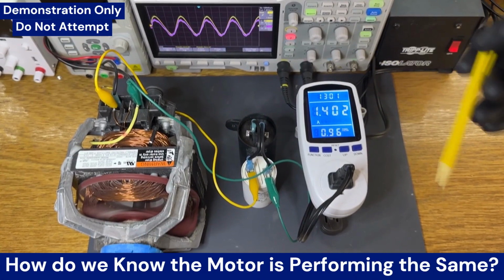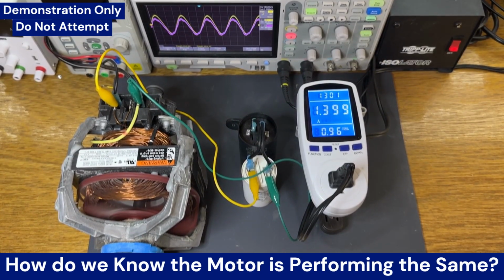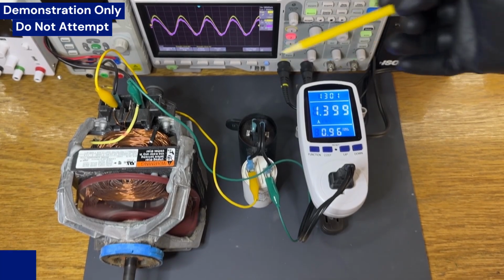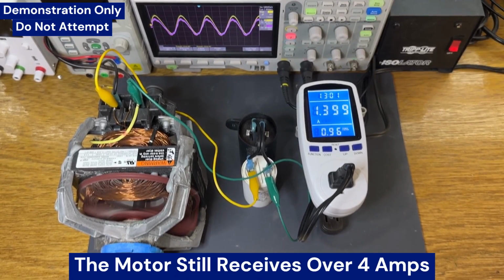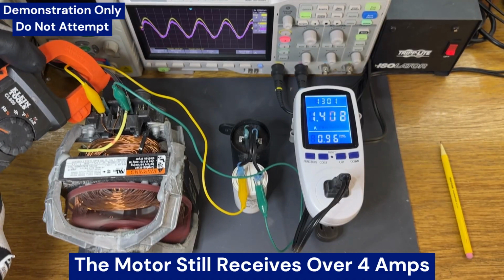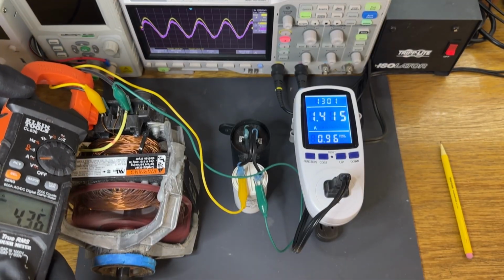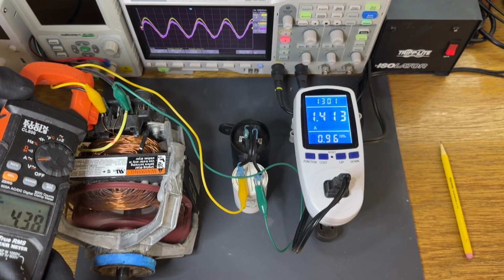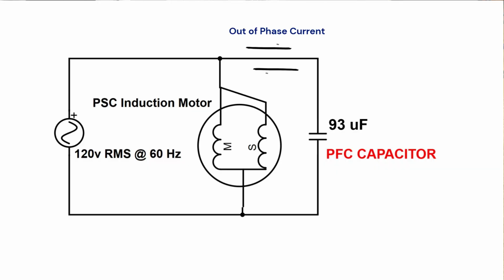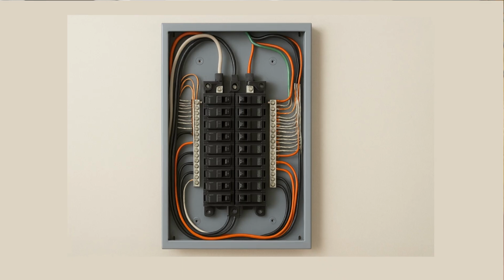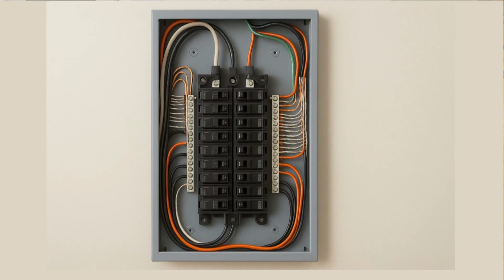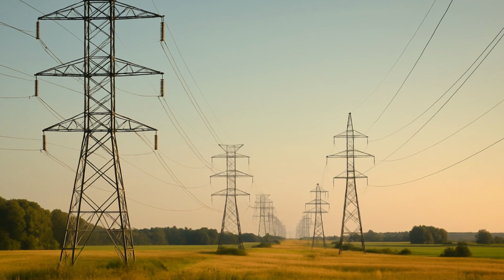You might be wondering, well, if the motor is only drawing 1.4 amps, how do I know it's still performing the same? Well, if I use this clamp meter right here at the motor terminals, you'll still see that it's drawing over 4 amps just like before. Here's what's happening. The out-of-phase current is now circulating between the motor and the capacitor, not between the motor and the utility company. The motor still behaves the same. It still gets the original current, but the power source now only has to supply 1.5 amps of in-phase real current. This reduces resistive losses in your home's wiring and along the utility's power lines.